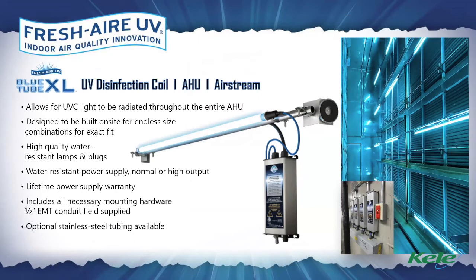So the lamps themselves range in size from 12 inches to 60 inches. They are high output UVC lamps. And as you see there, we have different options available, such as the magnet or the 12-inch bracket, which actually comes included in the kit. The power supply is 110 to 277 volt. And what's nice about the Fresh-Aire UV power supply is it could light additional lamps. So if you need two 60-inch lamps, then you could use one of our dual power supplies. You don't need one power supply per lamp. So it does make installation a lot more manageable as far as installation and installation costs.